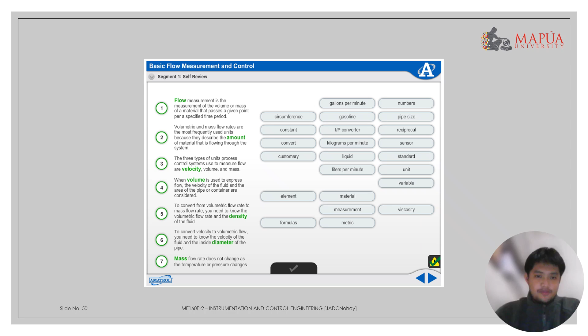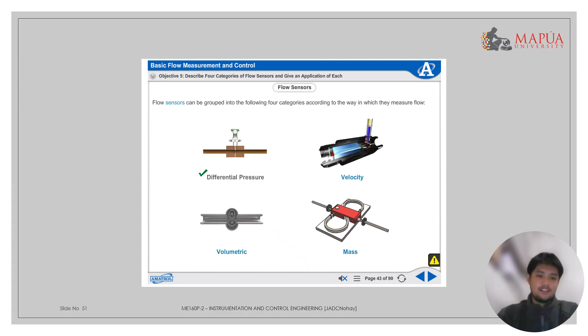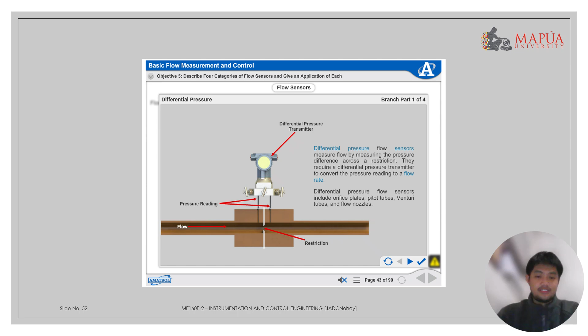Now for the flow sensors. Flow sensors can be grouped into the following four categories according to the way in which they measure flow: differential pressure, velocity, volumetric, and mass. Differential pressure flow sensors measure flow by measuring the pressure difference across a restriction. They require a differential pressure transmitter to convert the pressure reading to a flow rate. Differential pressure flow sensors include orifice plates, pitot tubes, venturi tubes, and flow nozzles.